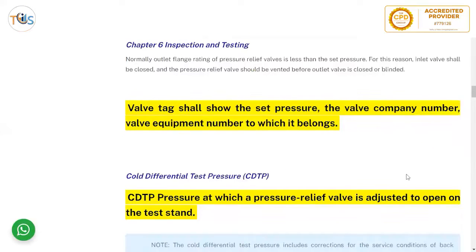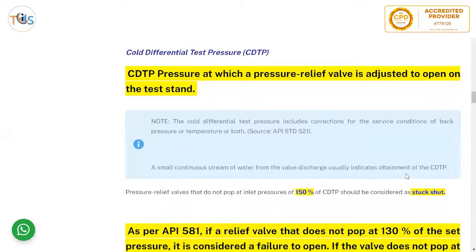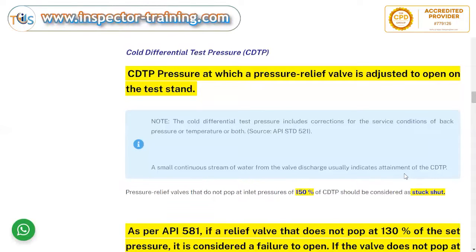Chapter 6 covers inspection and testing. Normally the outlet flange rating of pressure relief valves is less than the set pressure. For this reason the inlet valve shall be closed and the pressure relief valve vented before the outlet valve is closed or blinded. The valve tag shall show the set pressure, valve company number, equipment number to which it belongs, and the Cold Differential Test Pressure (CDTP). CDTP is the pressure at which the pressure relief valve is adjusted to open on the test stand.